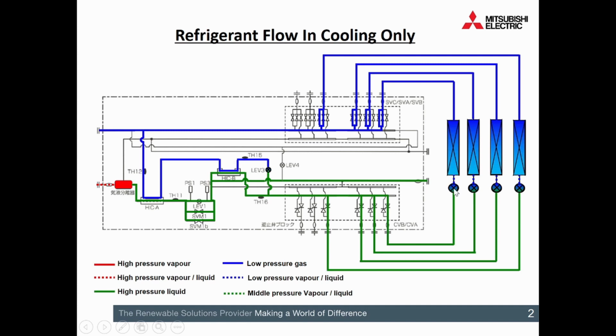As it passes through our expansion device, we're going to go from the high side down to the low side, but we actually aim it so that if the indoor unit is more than 2 degrees from set point, this is actually a flooded evaporator. So although we had that big pressure change, and it's aiming for around about 7.2 bar, which is 0 degrees evaporating temperature, we're actually trying to have a flooded evaporator. And that is the case until the indoor unit gets within 2 degrees of set point.